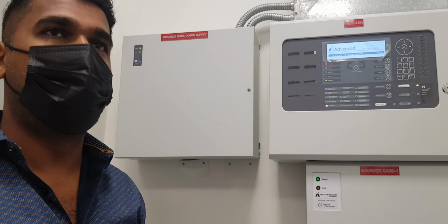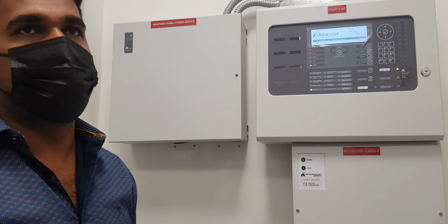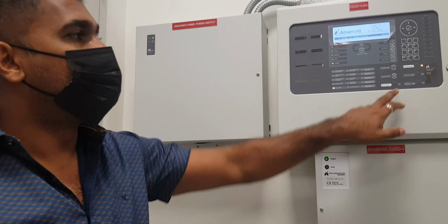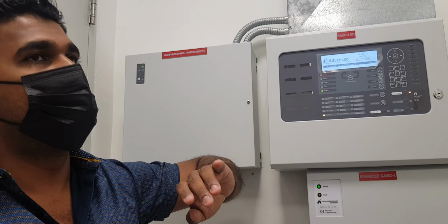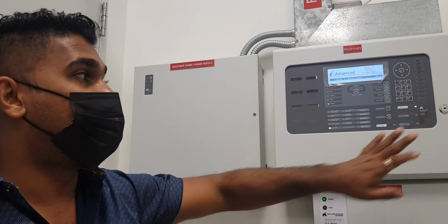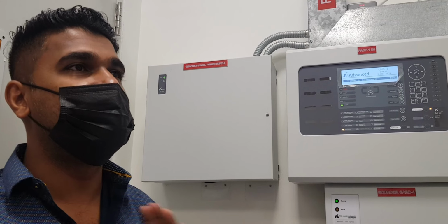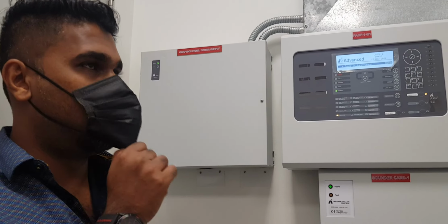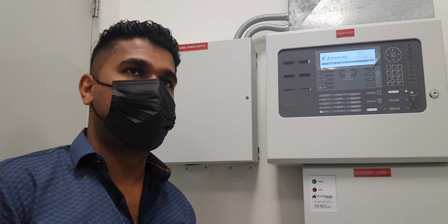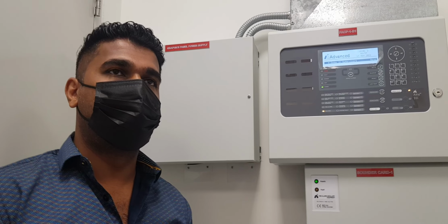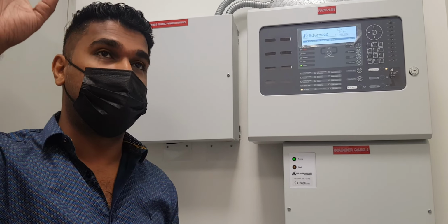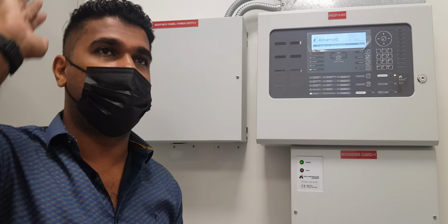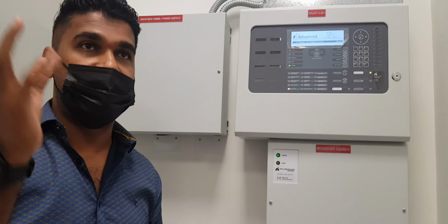Even if you don't silence the panel, once you press this before 15 seconds, it will allow you 180 seconds. If you don't, after 15 seconds cause and effect will start. So there is no sounder, flasher or evacuation message immediately at the alarm? Only in the bedrooms. In the suite rooms, all the guest rooms, there are sounder bases.